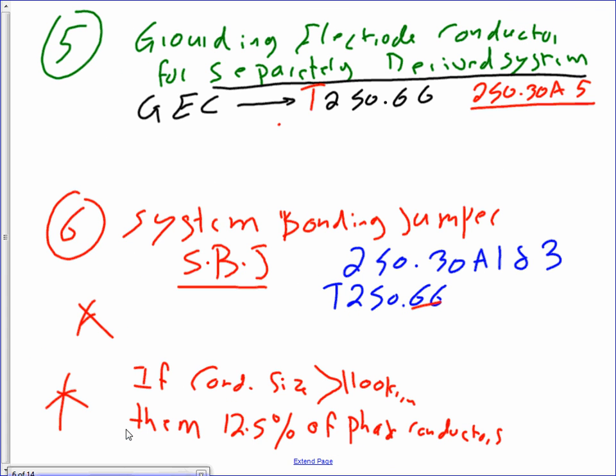Okay, so the next one, guys, is called grounding electrode conductor for separately derived system. It's called separately derived system because we have a delta and a Y, and there is no connection. Here's the delta, 3 wires, 4 wires coming out of the Y, and there is no connection between them whatsoever. Nothing. They're not electrically connected to each other. They are coupled together, guys, through electromagnetism. Welcome to the Tesla world, huh? Coupling them together through electromagnetism. That's a separately derived system. So you're supposed to ground the neutral.